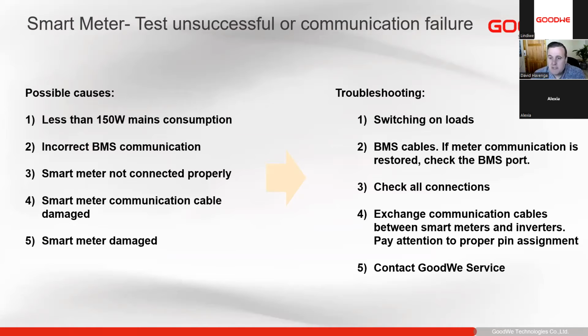So next, the smart meter test. Very often the smart meter test does fail or it gives us incorrect results. The causes for this could be, so we need to make sure that we are consuming power from the utility. So at least 150 watts per phase. It's always recommended maybe to switch your PV off and put on as many loads as you can to make sure that we are consuming from the utility. If you then run the meter test, while we can see a lot of consumption from utility on all our phases, then the meter test should be able to be performed accurately.